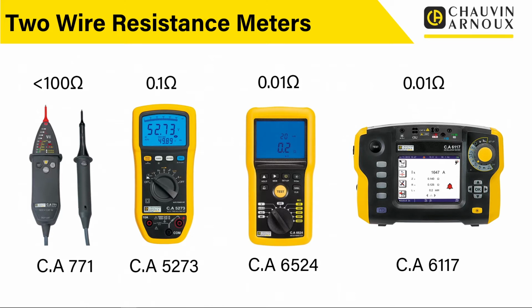We could start to identify a lot more problems with electrical installations. Even things like ring main tests, we could do a hell of a lot better job on if we had a tester with that extra degree of accuracy, because it would tell us a lot more about what was going on with the installation. It would give us a lot more confidence in that environment. So there is a debate, and I'm just sparking this debate because there's a standard, it's there, and it says that things are done in a certain way. But when you look at using these 2-wire tests, which are the industry standard for doing those tests, I think we are missing a trick by not doing these tests in a bit more detail and getting the additional information that we could gain by using a more accurate method.